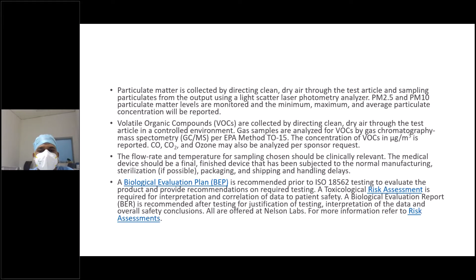These are also tested at the flow rate and the maximum temperature. If we keep the flow rate at minimum and the temperature at maximum, there are chances of more concentrated vapors being delivered. So it tests the worst conditions for VOCs and particulate matter. ISO 18562 offers a common sense and risk-based approach to medical devices that communicate with the gas path, which contacts the patient's tissues.